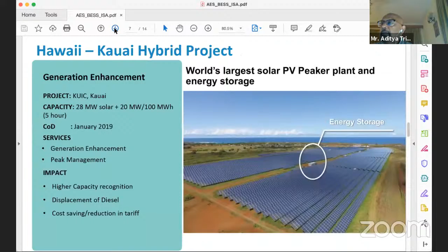See the response. The dark blue is the response of energy storage. As the frequency goes down to 50 or below, as soon as it goes back to 50, energy stops discharging from the asset. As soon as frequency goes down, it starts pumping up. Remember, 10 megawatt is not a huge thing, but it proves that within less than 100 milliseconds, we supply full capacity of energy storage to the grid. This is to prove that frequency response is real. We shared this with the regulators, and they were very surprised because they don't have this curve. Anywhere in India, I have not seen any curve where an energy storage asset has responded to grid frequency like this, but here we have many such examples.